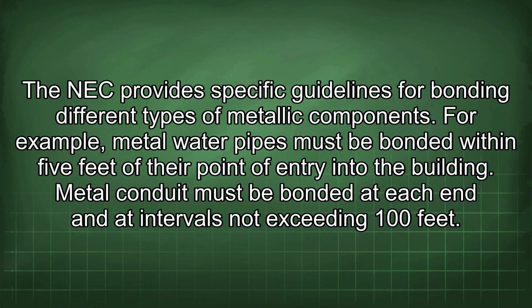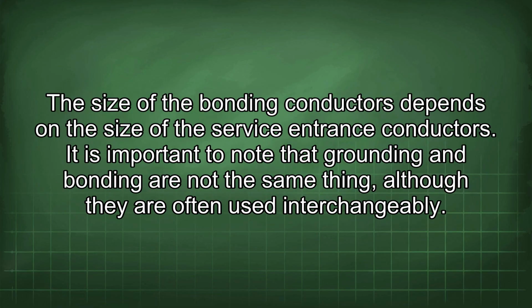The NEC provides specific guidelines for bonding different types of metallic components. For example, metal water pipes must be bonded within 5 feet of their point of entry into the building. Metal conduit must be bonded at each end and at intervals not exceeding 100 feet. The size of the bonding conductors depends on the size of the service entrance conductors.